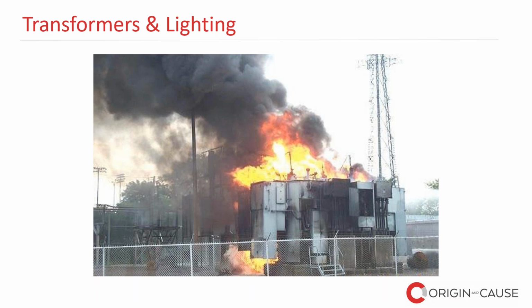In short, following our investigation, we determined that the new models had been installed without properly assessing the old system. The new transformers were not adequately rated for the electrical system and thus were incompatible. This resulted in noise polluting the source, which resulted in overheating in the transformers. The issue was rectified once the transformer was replaced with the properly rated equipment. What's interesting to note is that there are certain regulations to prevent issues like this from happening. In Ontario, transformers over 1,000 volts need to be properly rated, sized, and the plans need to be reviewed with ESA. For this file, there was a great subrogation opportunity as the installer should have been aware of the regulations and the ratings.